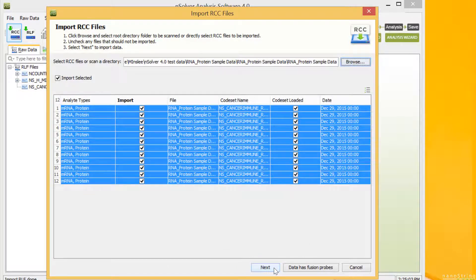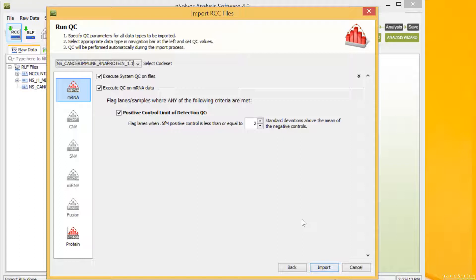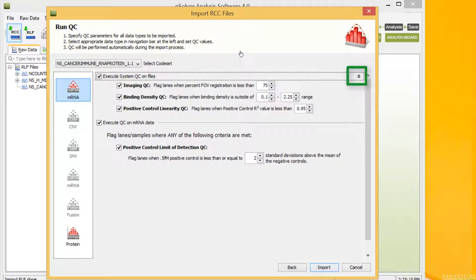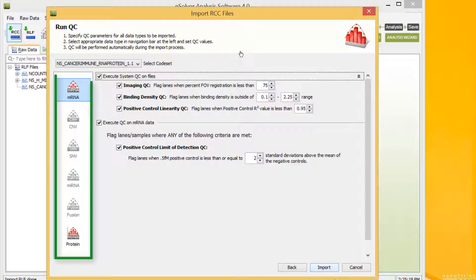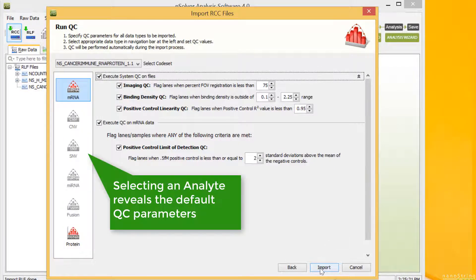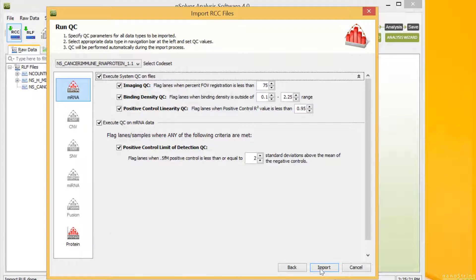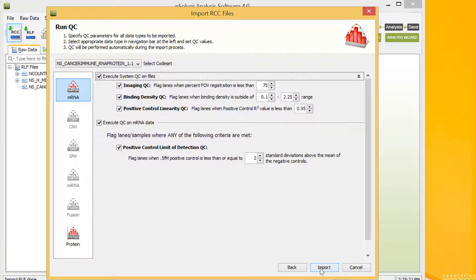Select Next. This automatically brings up the QC window. We need to use the double arrow icon in the right corner of the screen to reveal the top three system QC parameters. The activated buttons in the panel of analytes along the left side of the window represent the analytes detected in your data. Selecting an analyte reveals the default QC parameters associated with it. You may change QC parameters, but this is not usually recommended nor necessary. Select Import.